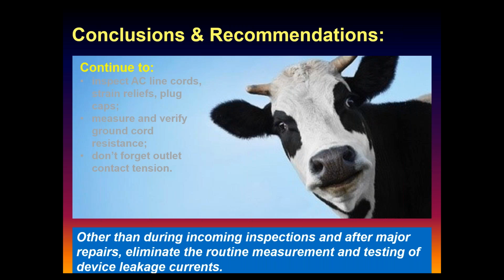So you're going to have a much larger reading as a result of that stray capacitance, degrading the isolation. Theoretically it should be zero. So when the isolation monitor alarms, it becomes something that will maybe last one minute with high leakage and high stray capacitance causing it - it's not even a current that's flowing yet, it's a current that would flow if you had a line-to-ground fault.